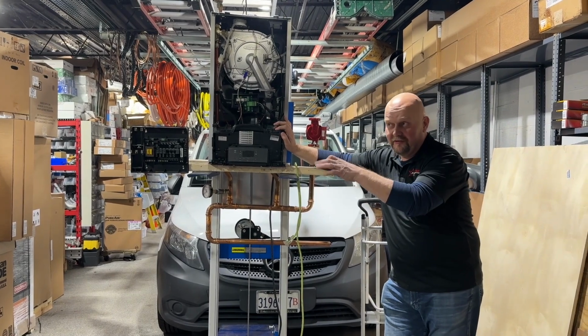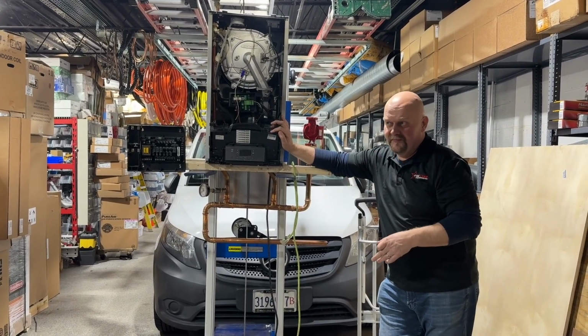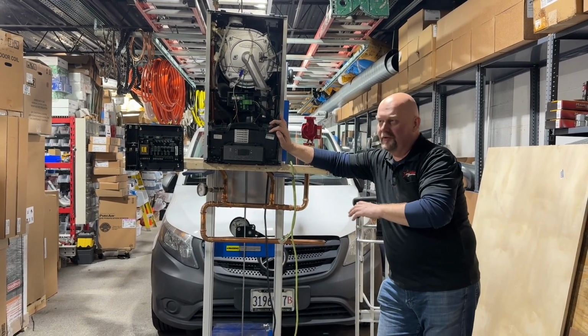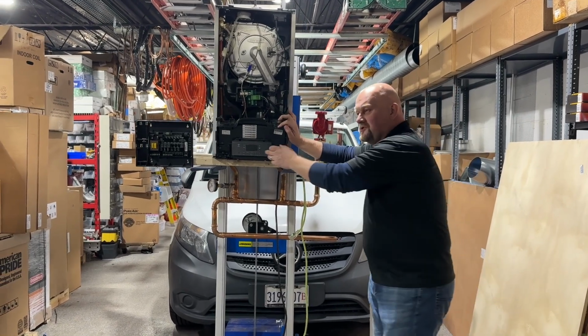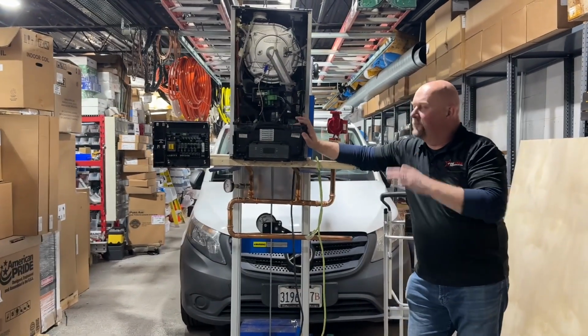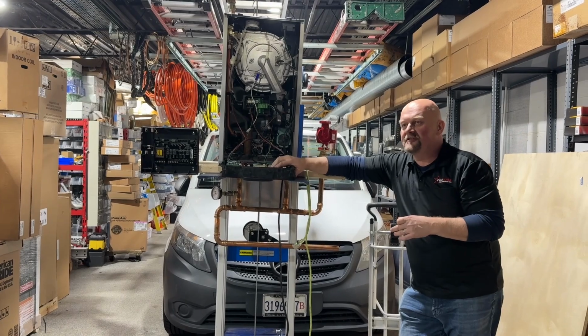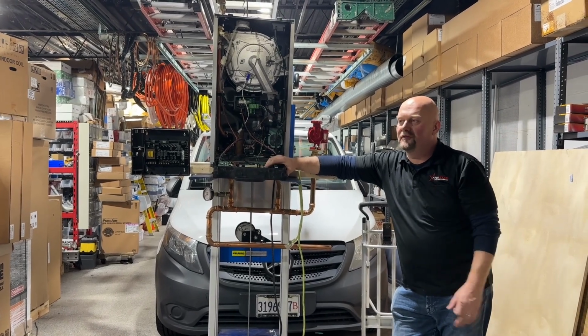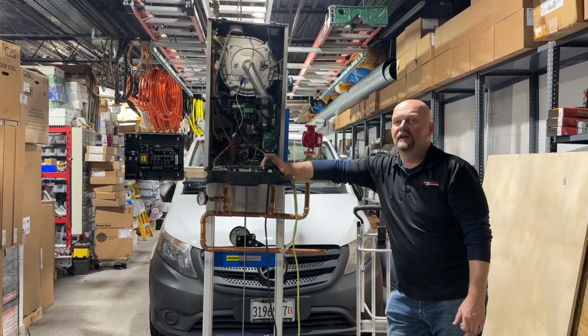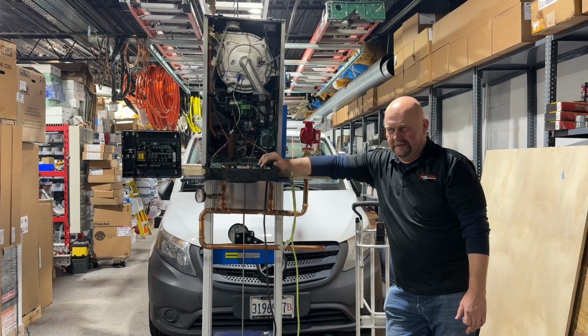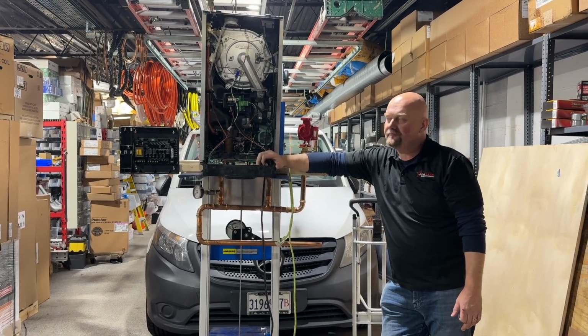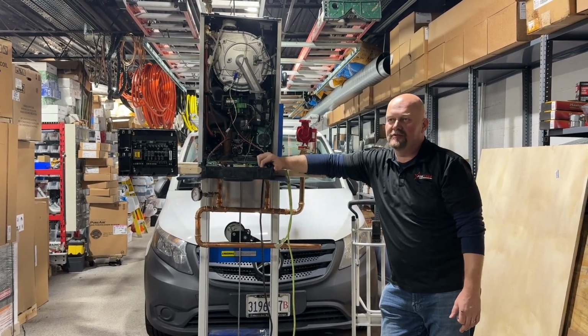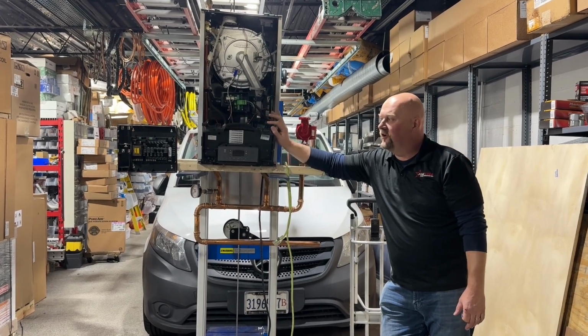Do you remember how you and I were flushing over on Greenwood, and we were actually getting the pressure up in order for us to flush things out? It was a digital display of the pressure. Most of these boilers now are pressure sensitive. They won't operate unless you have 14 pounds of pressure. Not even 12. They want 14 pounds of pressure. I don't know why, because we've always been taught to do 12 pounds of pressure, but they give you a fault if you're under 14.